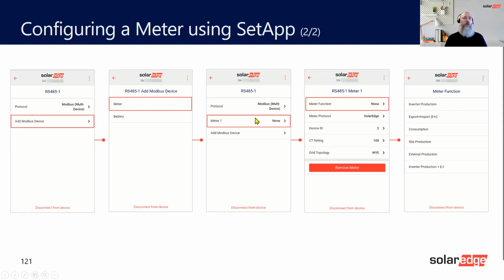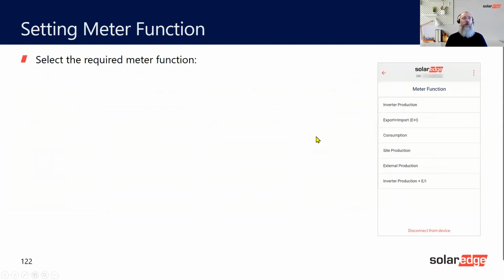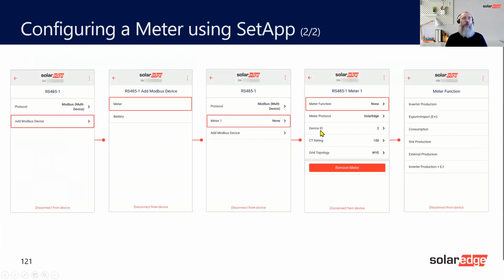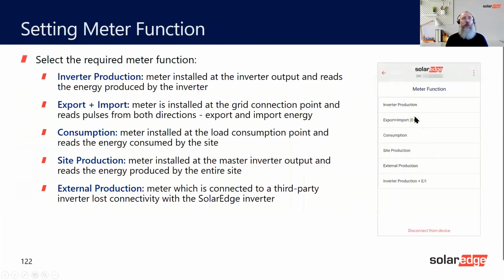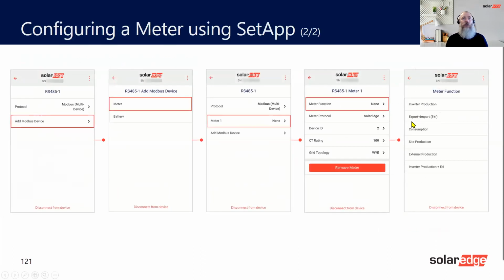What you'll notice, because it says meter 1, you'll also see, whoops, go back, it will say device ID 1. So you'd have to change this to 2. Do you remember how the meter has a dip switch of 2? It was set to ID 2. The CT should automatically happen, and then you just choose what one. We always recommend export and import as the best one. That's what we recommend you use.